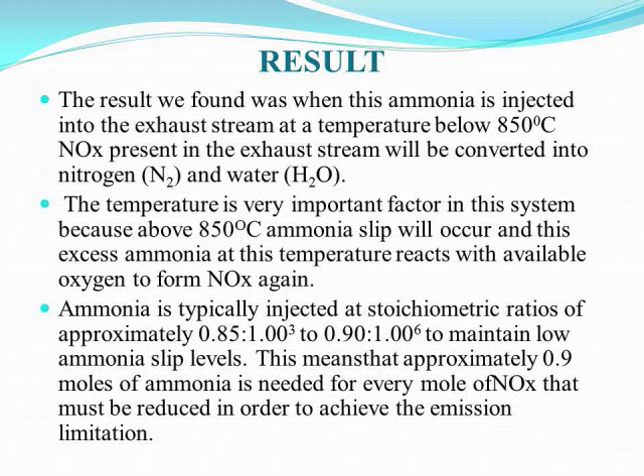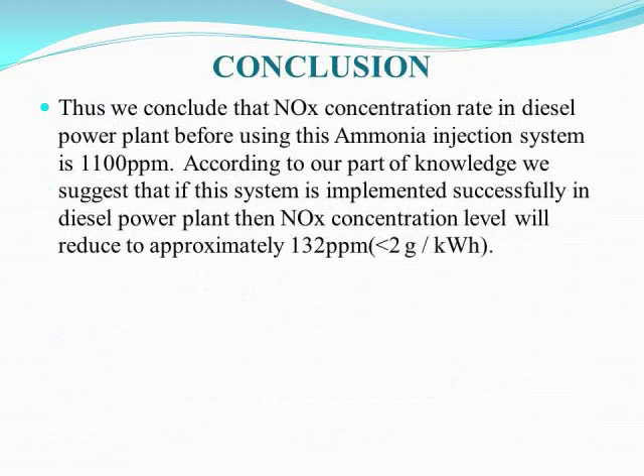The results show that if ammonia is injected below 850°C, ammonia slip can be reduced, and the injected ammonia will react with NOx in the exhaust gas to form nitrogen and water, which are harmless for the atmosphere. The important parameter is that ammonia should be injected at a stoichiometric ratio of 0.85 to 0.9 — with 0.86 being the optimal level to minimize ammonia slip.